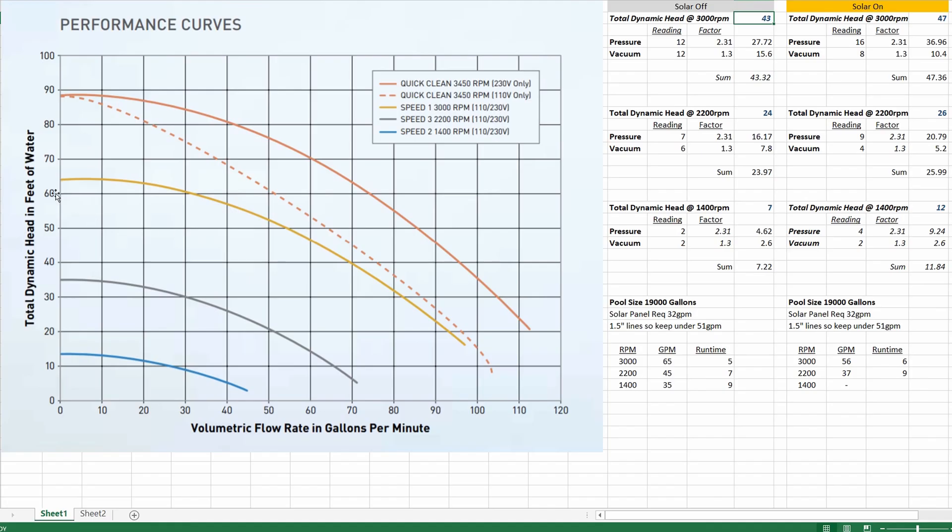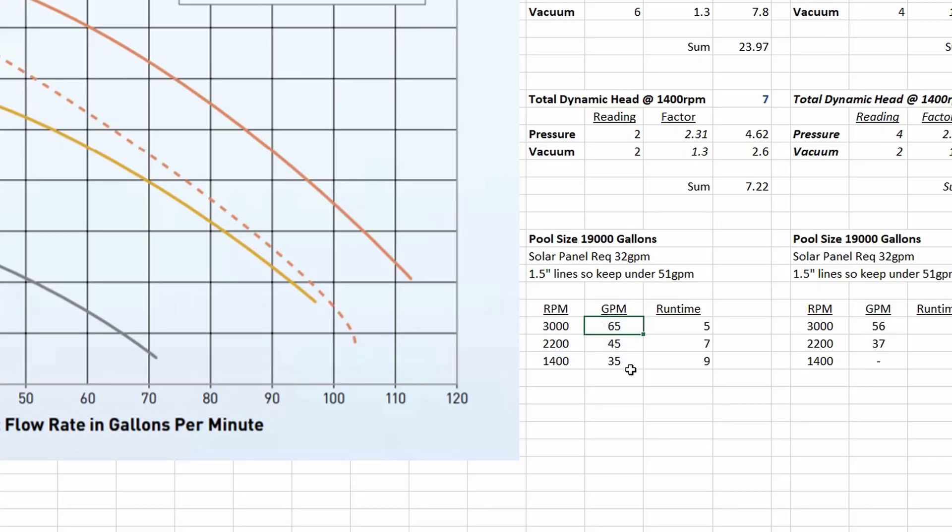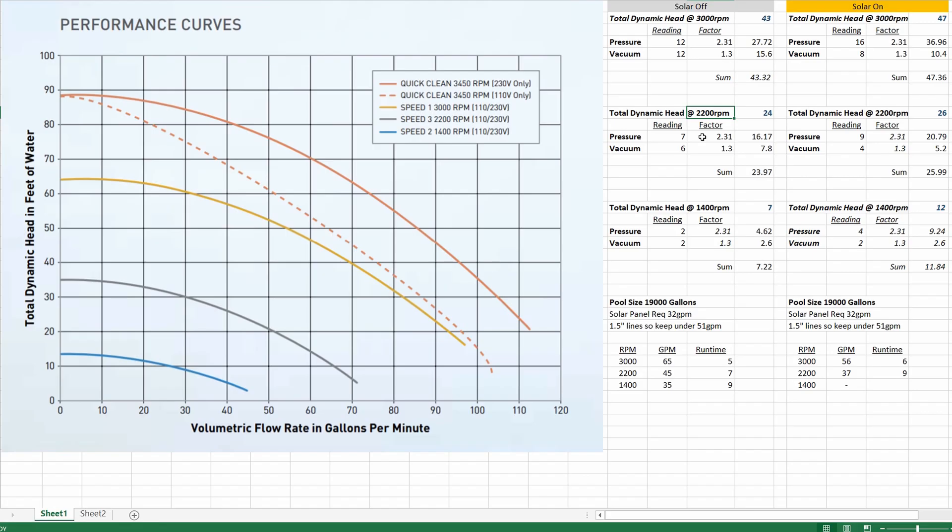So if we look on the left side here for the 3000 RPM curve which is this gold color here and look for where we'd say about 43 lies on the graph about here and track over you can see that we land somewhere between the upper 60s to just under 70 gallons per minute. So I'll call that about 65 gallons per minute down here at the bottom.